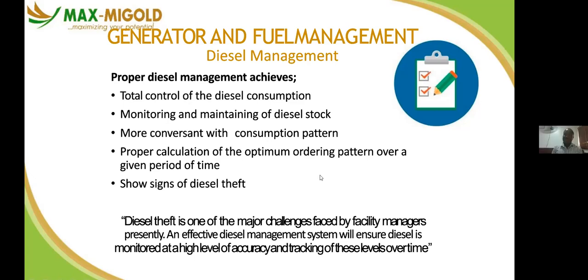If it's 500 kVA, you multiply it by 1.4, it gives you about 700. If it's 1,000 kVA, you multiply it by 1.4, it gives you 1,400. That's the maximum amperage that can be drawn from your generator. All right, thank you. Let's proceed.